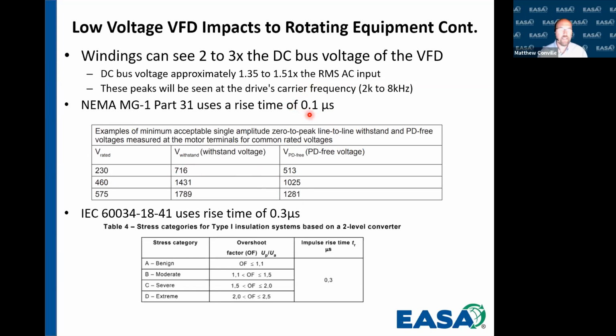Now, IEC is a little bit different. So on the 60034 standard, it tells us in 18-41 that it's going to use a rise time of 0.3 microseconds. And when we're on a converter, or what we would call a drive system, they give 4 different stress categories that are standard, which is A, benign, B, moderate, C, severe, and D, extreme. They also have one for S, which is specific.